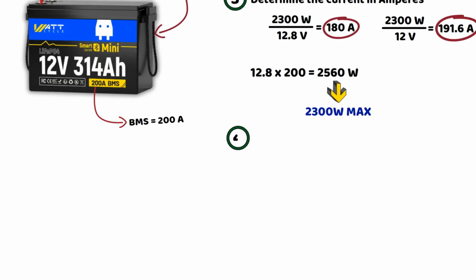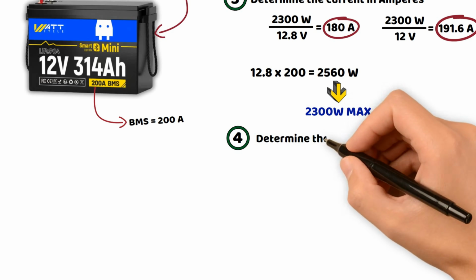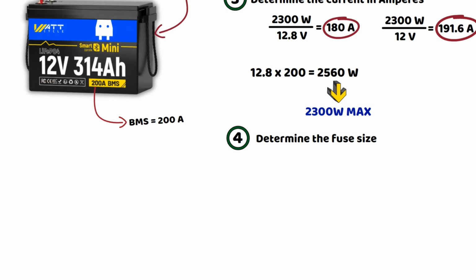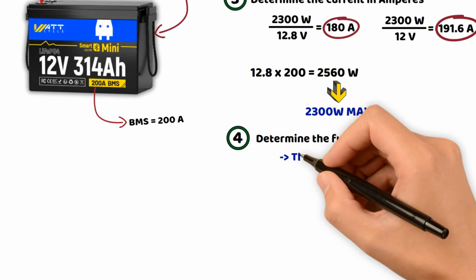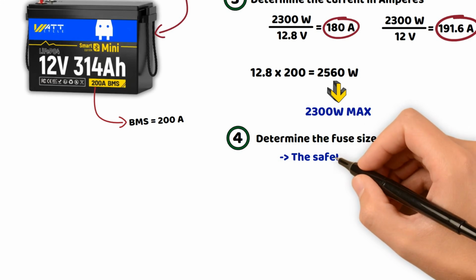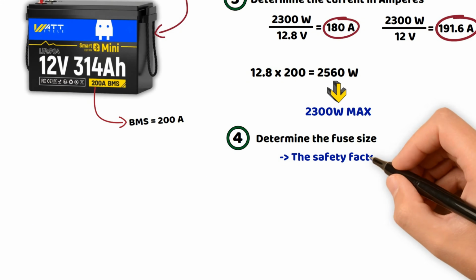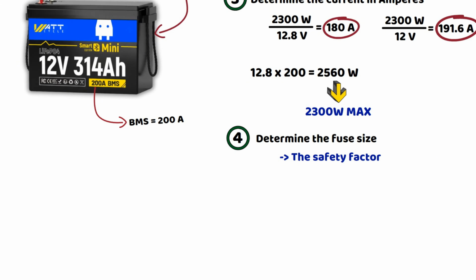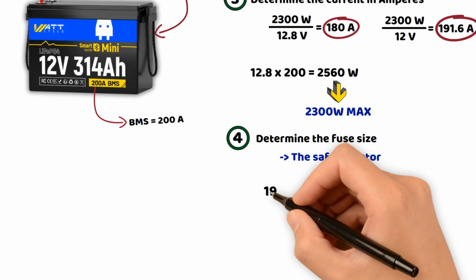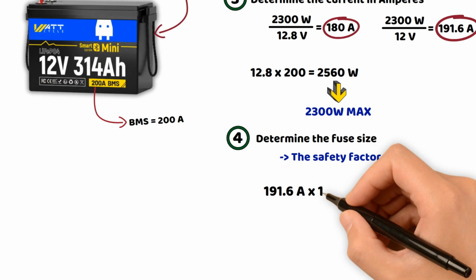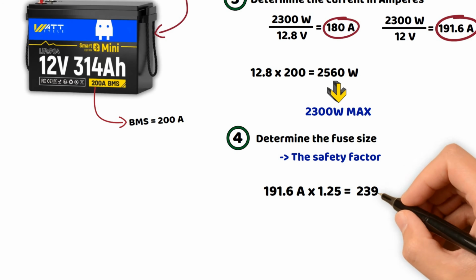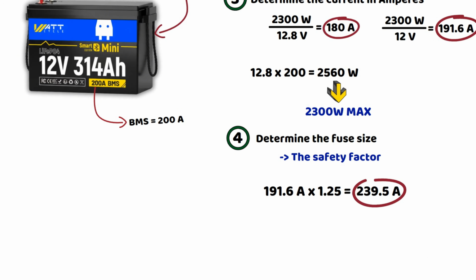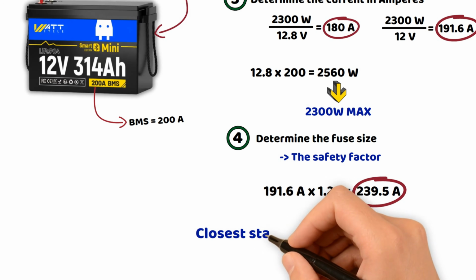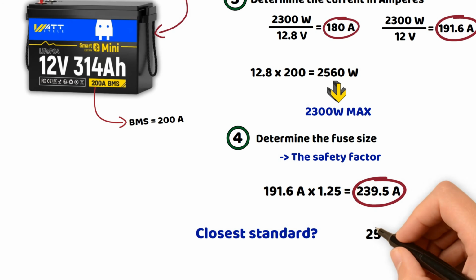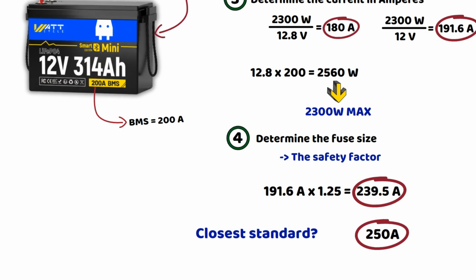Step 4. Determining the fuse size. Now that we have the maximum value in amperes, we apply a safety factor of 1.25 or 25% to prevent the fuse from overheating or blowing unnecessarily during prolonged use at full power. So 191.6 amperes multiplied by 1.25 equals 239.5 amperes. Now there is no fuse rated at 239.5 amperes. The closest standard fuse here will be 250 amperes. To keep it simple, we always round up to the next highest standard fuse size.